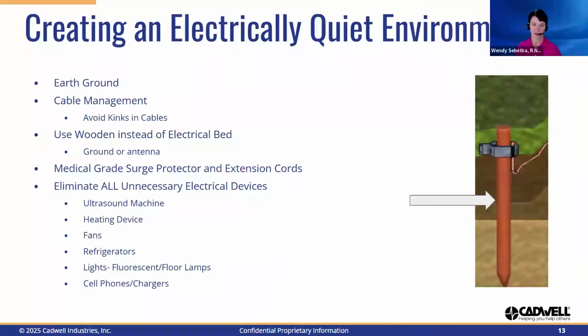Maintaining proper cable management by refraining from rolling the machine over the cables, neatly wrapping cables, avoiding kinks in the wires, and using Velcro strips or zip ties to secure wires in an uncluttered manner will protect your wires from non-visual damage. Any additional cables will increase the risk of noise entering your system, but when necessary, only medical-grade surge protectors and extension cords should be used.